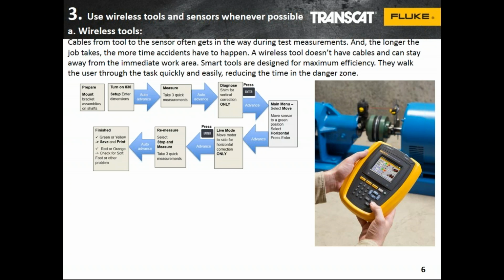We would just kind of eyeball it, put it back as close as we could. The problem is that a little bit of misalignment we feel we have to live with will quickly wear out bearings and seals. So if we never fix the root cause, we just keep replacing bearings and seals.